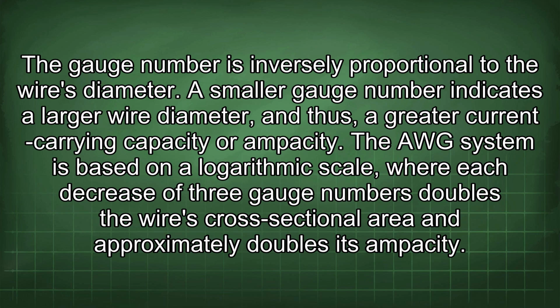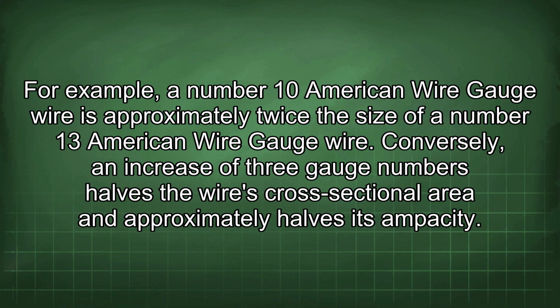The AWG system is based on a logarithmic scale, where each decrease of 3 gauge numbers doubles the wire's cross-sectional area and approximately doubles its ampacity. For example, a number 10 AWG wire is approximately twice the size of a number 13 AWG wire. Conversely, an increase of 3 gauge numbers halves the wire's cross-sectional area and approximately halves its ampacity.